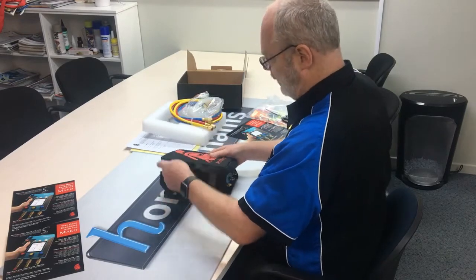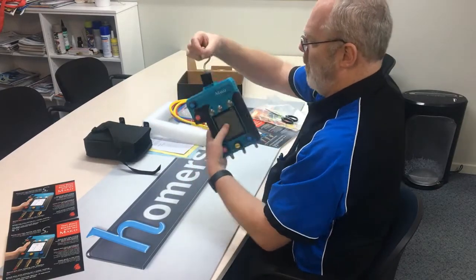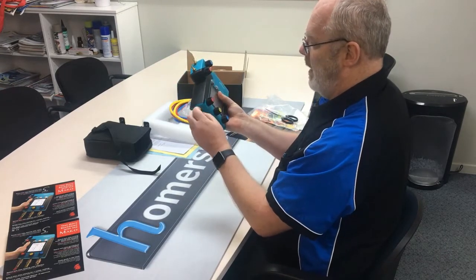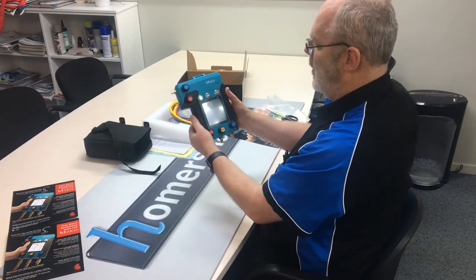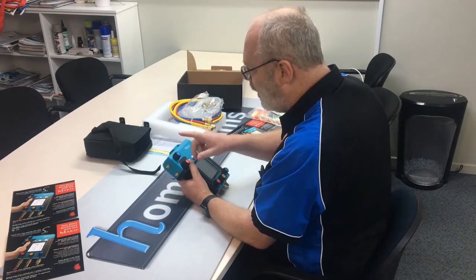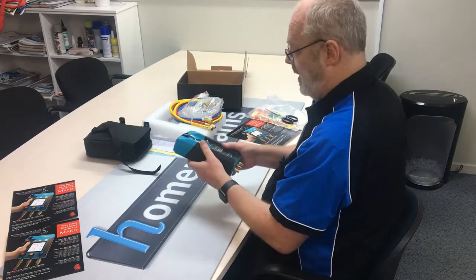Let's have a look at what we've got in here. Wow, look at this — feels kind of solid. On the top we've got a hanger hook, so when you're working you can hang this up on the place you're working. There are no batteries in this one, that's fine. Nicely done connectors at the bottom, three valves, and your two bleed valves at the top. This is your bypass valves to control high and low pressure and bypass, and your bleed valves.